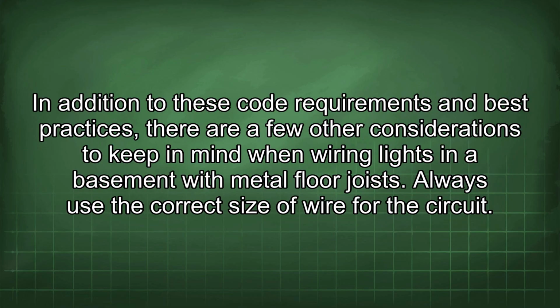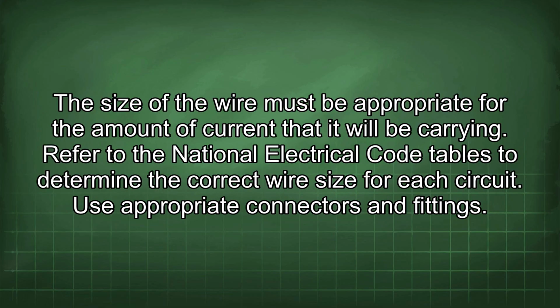In addition to these code requirements and best practices, there are a few other considerations to keep in mind when wiring lights in a basement with metal floor joists. Always use the correct size of wire for the circuit. The size of the wire must be appropriate for the amount of current that it will be carrying. Refer to the National Electrical Code tables to determine the correct wire size for each circuit.